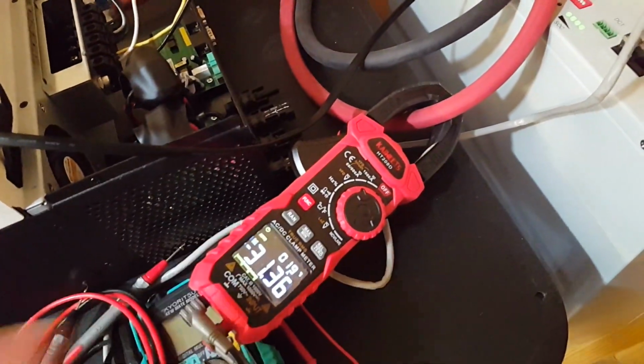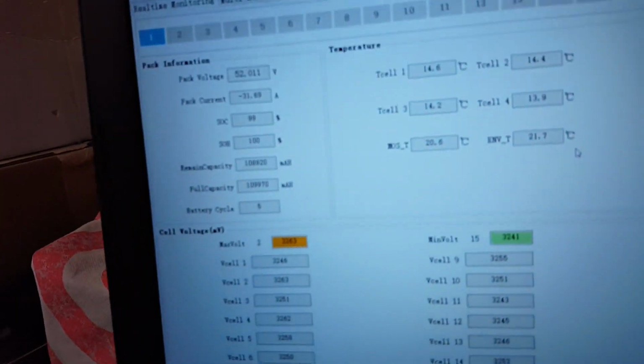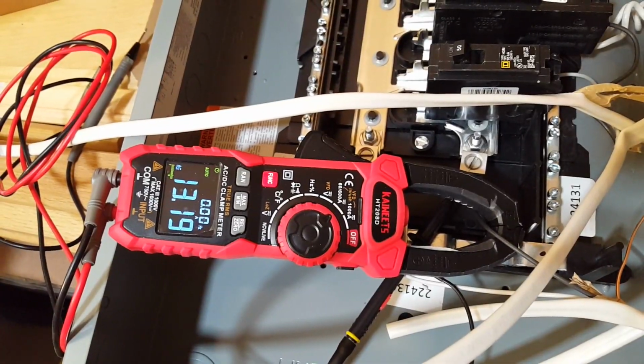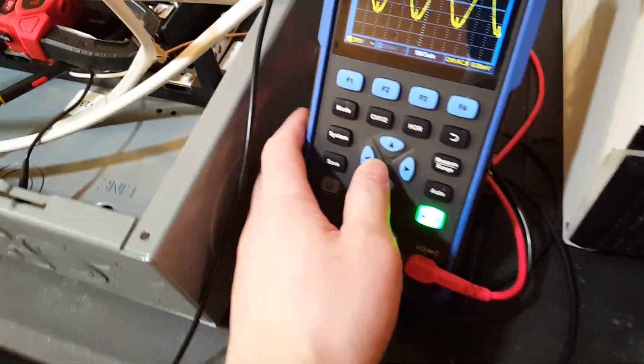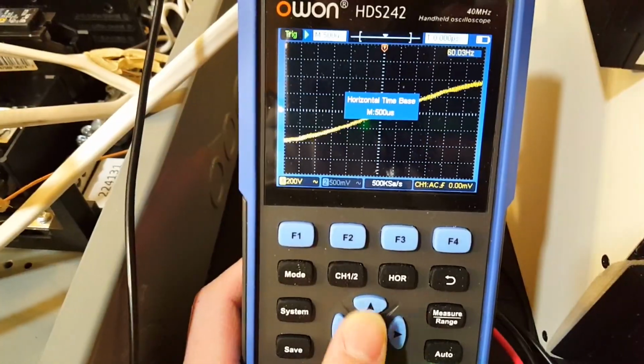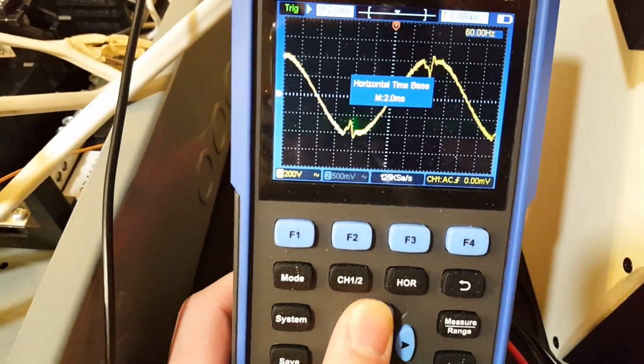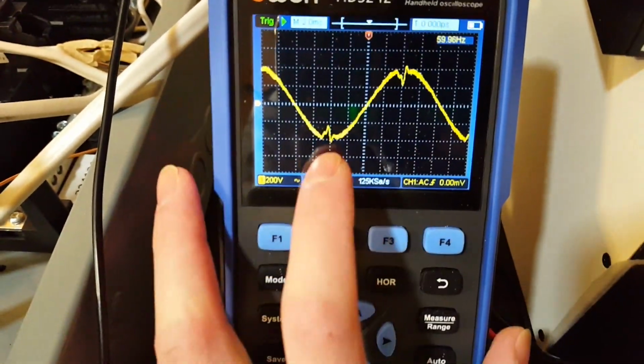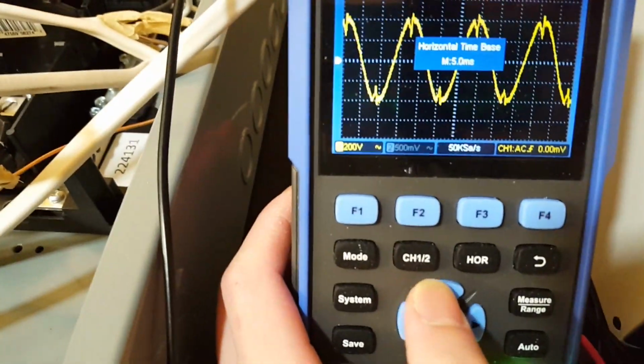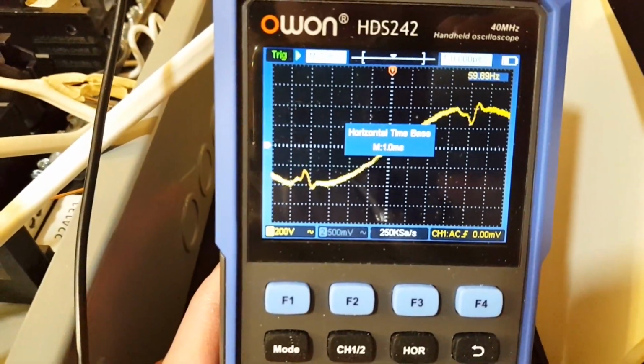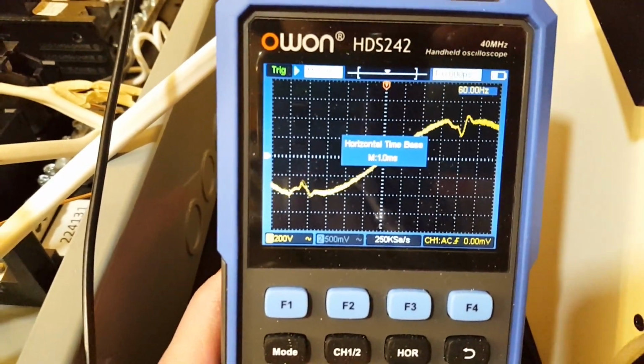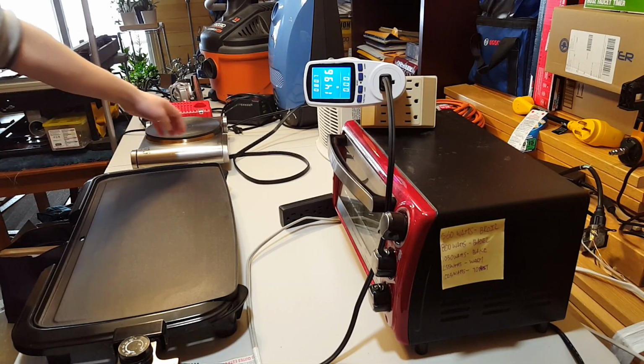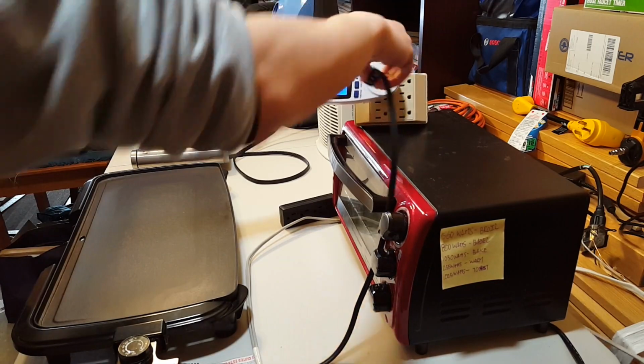On the battery, 31 amps. BMS software says it is doing 31 amps for the frying pan. AC amps 13. Okay, let's zoom in on the sine wave. Now this is in battery mode, so you can see there is ripple there on the peak. At the highest point of the sine wave, you see a little bit of a dip. If we go to a higher load, let's see if that will smooth out a little bit. Try this hot plate back here. So unplug that.